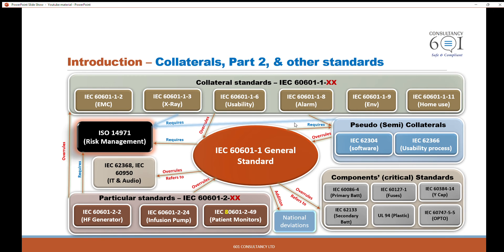You can see the arrows, and there are three phrases: overrules, requires, and refers to. When it says overrules — let's start from the particular standard — the particular standard overrules the collateral standard, and the collateral standard overrules the general standard.